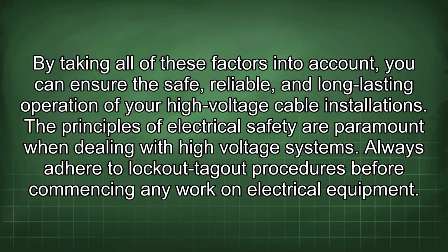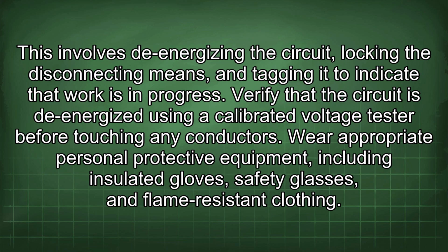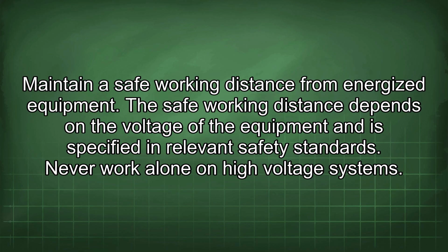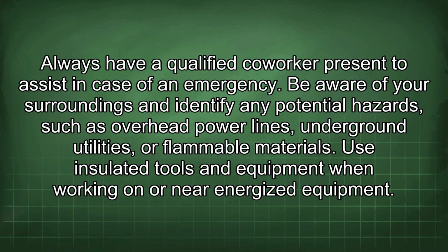The principles of electrical safety are paramount when dealing with high-voltage systems. Always adhere to lockout-tagout procedures before commencing any work on electrical equipment. This involves de-energizing the circuit, locking the disconnecting means, and tagging it to indicate that work is in progress. Verify that the circuit is de-energized using a calibrated voltage tester before touching any conductors. Wear appropriate personal protective equipment, including insulated gloves, safety glasses, and flame-resistant clothing. Maintain a safe working distance from energized equipment. The safe working distance depends on the voltage of the equipment and is specified in relevant safety standards. Never work alone on high voltage systems. Always have a qualified coworker present to assist in case of an emergency.